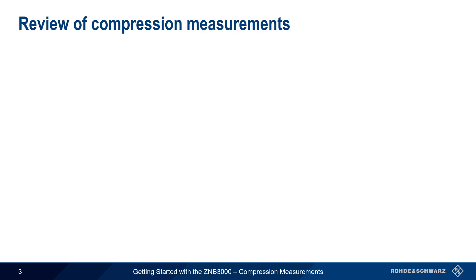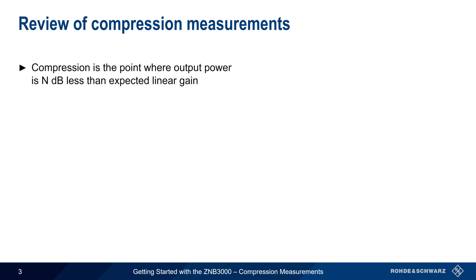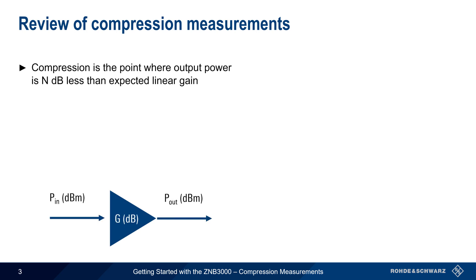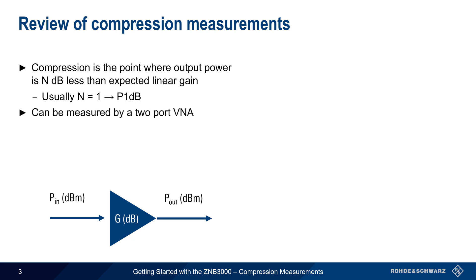Let's start with a brief review of compression measurements. Compression is defined as the point where the actual output power of a device — most often an amplifier — is N dB less than the expected output power, assuming a constant or linear gain. In most cases, N is 1, and compression is commonly quantified as the 1 dB compression point, or P1dB. There are several ways of measuring gain compression, but the most common and most accurate is using a two-port Vector Network Analyzer, or VNA.